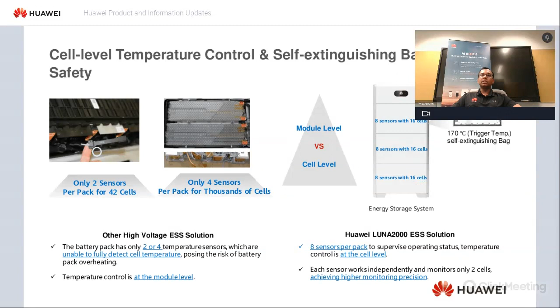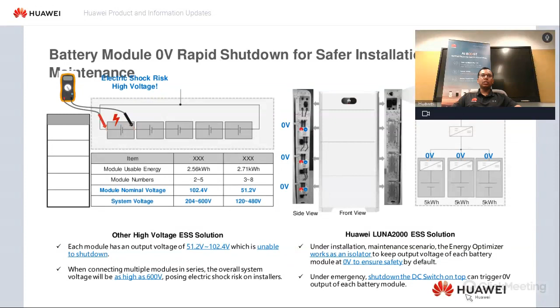There's 0-volt rapid shutdown for safer installation and maintenance. This is on the side of the battery here, emergency shutdown to 0 volts. Under an installation or maintenance scenario, the energy optimizers work basically as isolators to keep the voltage of each battery module at 0 volts to ensure safety. Under emergency shutdown, the DC switch is on top, and it can trigger 0-volt output on each battery module.